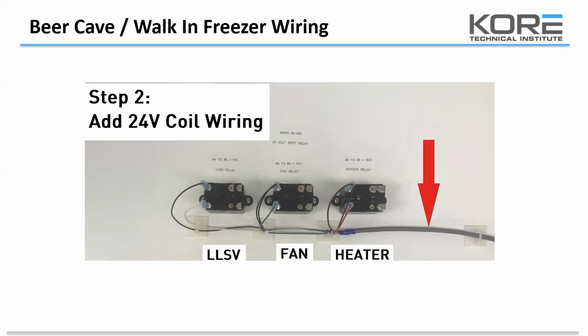On this particular picture, you'll see that we have brought in the low voltage wiring and have hooked up to terminals 1 and 3 on each of the peanut relays. We are using the black as the common. The 24-volt power source is located at the EMS panel or the SSDI panel in the new stores. Starting in about, I believe, April of this year, we went straight to a 24-volt control system away from the line voltage that we were putting through the wire.